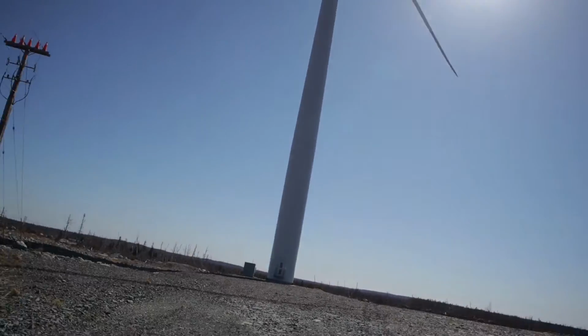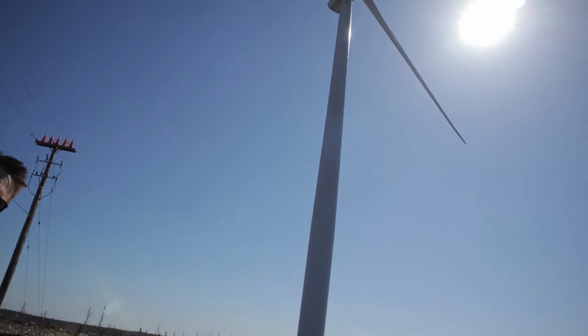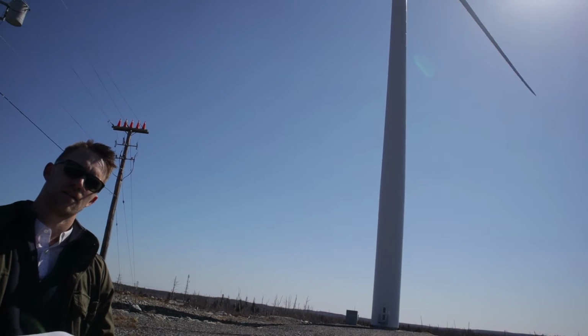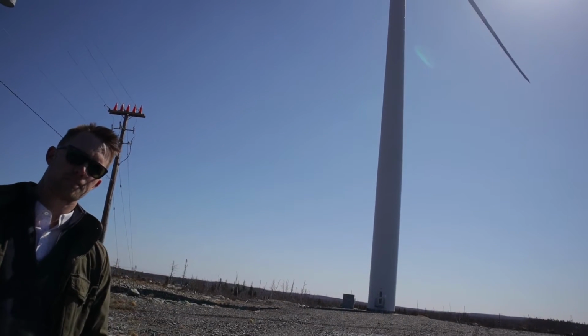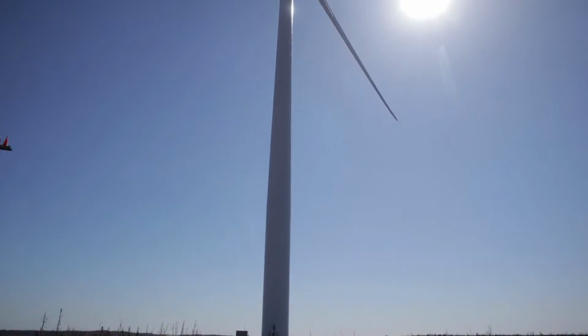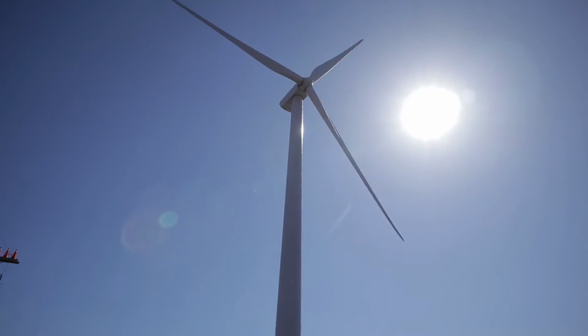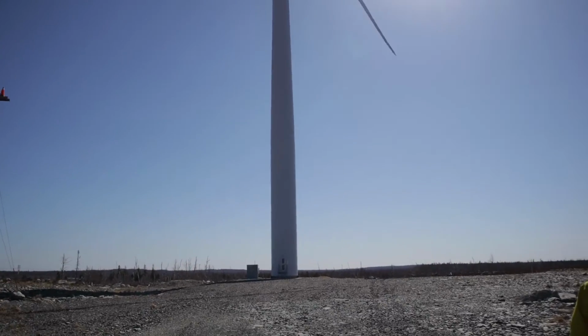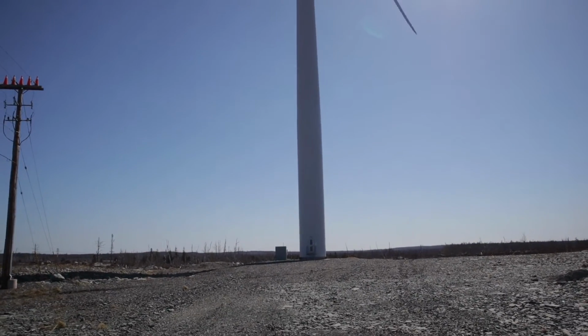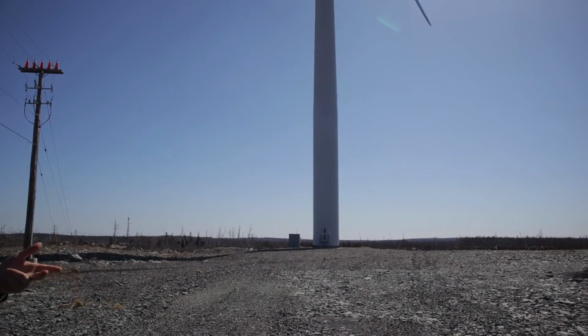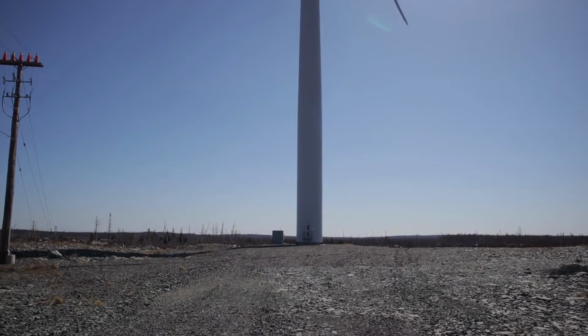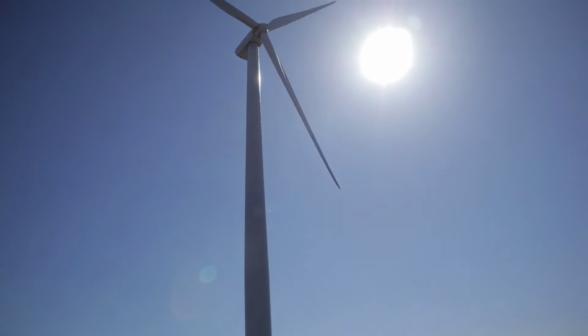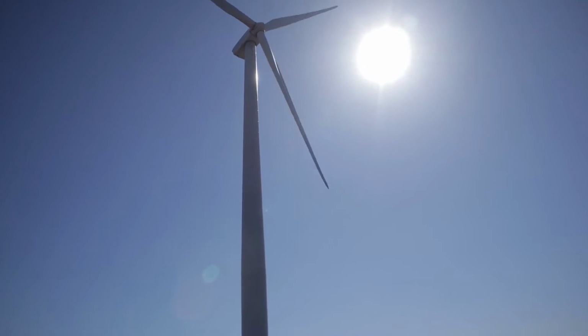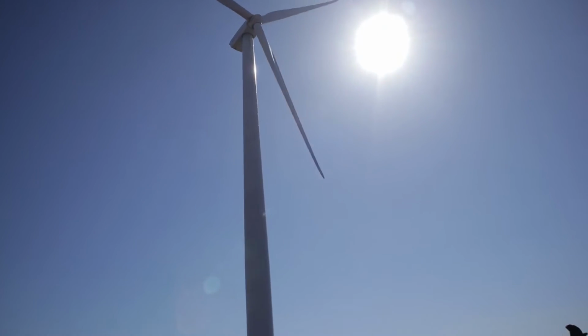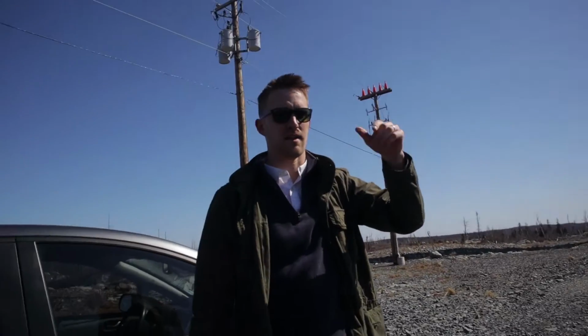Any questions on the nacelle? For the transformer, I do believe these are quite large in capacity already. Is the transformer at the back of the nacelle? In this case, everything in the tower is 690 volts. There is a small transformer down tower to give you 400, 230, 120. There's no 480 in these towers. So we have 400, 230, 120 down tower, and then we just send that up tower. So there are no transformers up tower, with the exception that the pitch system has a transformer set for each blade, just to get to a different working voltage.